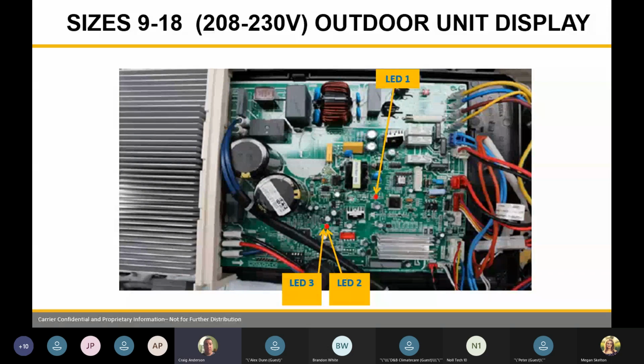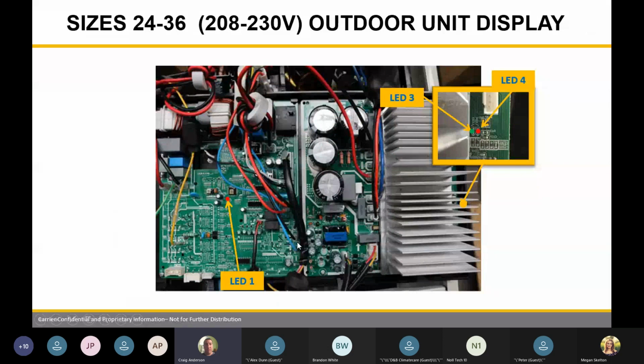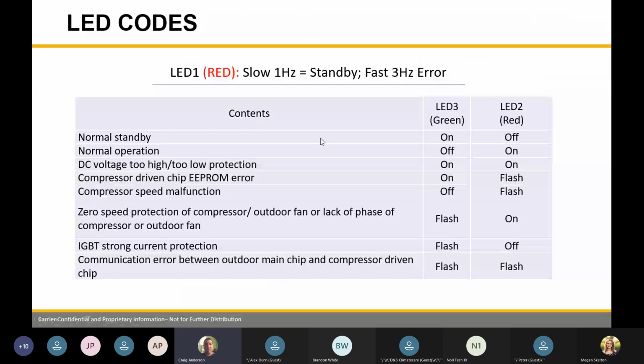24s and 36s. This is where you see we have 2 separate boards. We have a main board and we have an inverter board. You can see the separation in between the 2 boards. So we're going to be looking for LEDs on each board. So each one will tell us different codes. So here gives you an idea of what some of the codes are. Normal standby, so you have a red LED or a green LED, it's going to be flashing or it's going to be on. So that gives us an idea of where we're going to look.